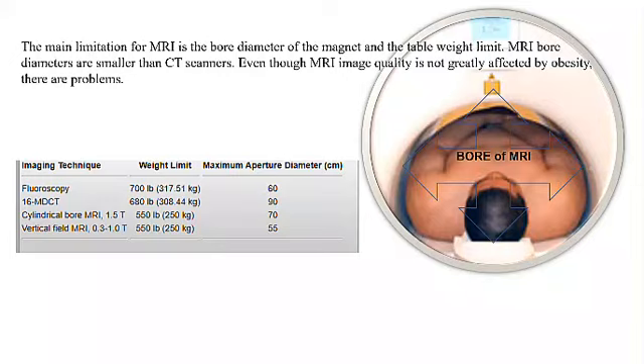The main limit for MRI is the bore diameter of the magnet and the table weight limit. Today, we have much greater diameter bores. In fact, we have what's called a wide bore magnet, which has a much larger aperture than what we used to have. The wide bore was developed not only for the obese patient, but for those patients that have claustrophobia. With a smaller bore magnet, it is easy to get claustrophobic inside the MRI scanner.